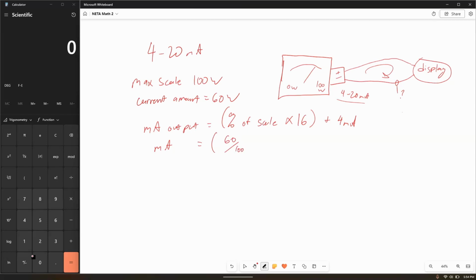It could be any unit, it could be any scale. We're going to do that times 16 plus 4. In this case, this one's pretty easy. This is 60%, so 16 times 0.6 is 9.6 milliamps of the amount of usable scale that we have, plus our deadband, our offset of 4. That means at 60% of scale on our meter, we've got 13.6 milliamps going through our transducer circuit. If you get a similar sort of question, hopefully that'll just ring a bell and make it a little bit easier for you to solve.